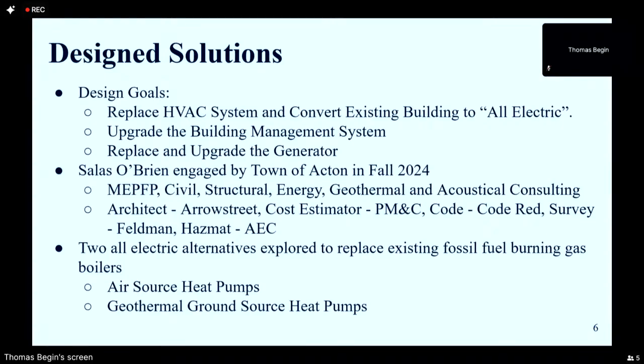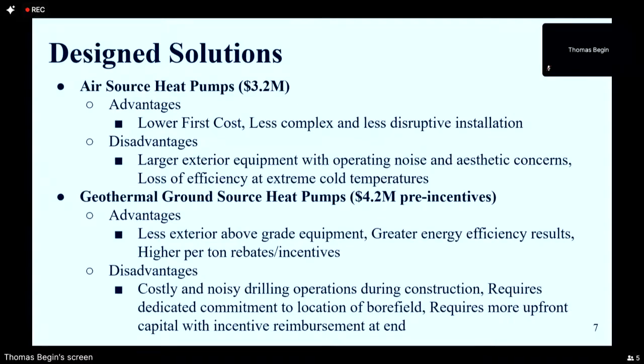So the alternatives that we looked at to replace the existing fossil fuel burning gas boilers and the existing chillers are an air source heat pump, which draws heat from the air and rejects heat to the air through site-mounted equipment, or a geothermal ground source heat pump, which uses wells basically drilled in the earth to store heat and pull heat through the different seasons. So we analyzed those two options in a conceptual study, which the next slide starts to outline, a few of the advantages and disadvantages that we presented to this committee, to the town for evaluation before proceeding into later stages of design.